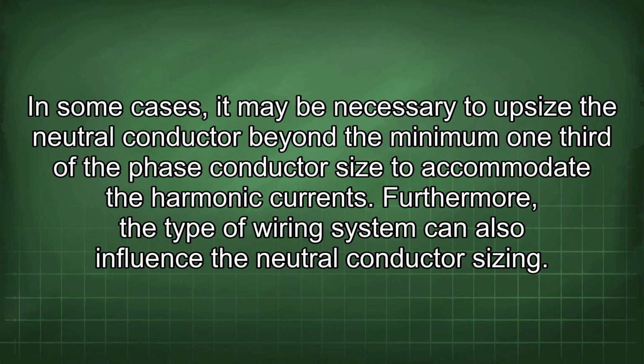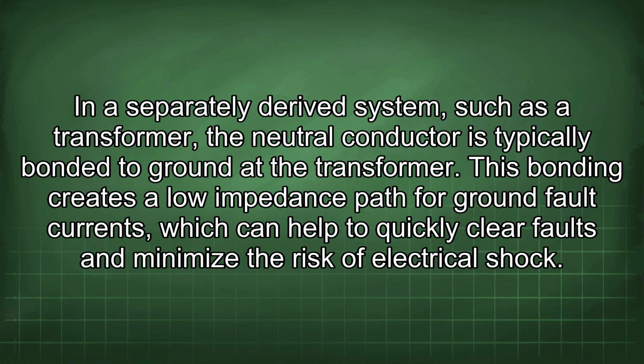Furthermore, the type of wiring system can also influence the neutral conductor sizing. In a separately derived system, such as a transformer, the neutral conductor is typically bonded to ground at the transformer. This bonding creates a low impedance path for ground fault currents, which can help to quickly clear faults and minimize the risk of electrical shock.